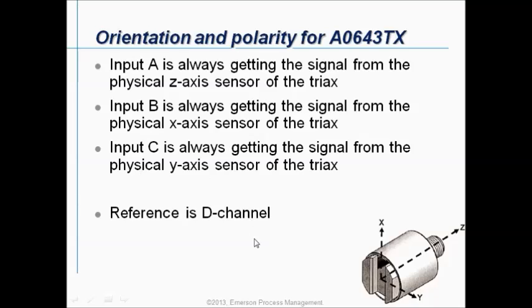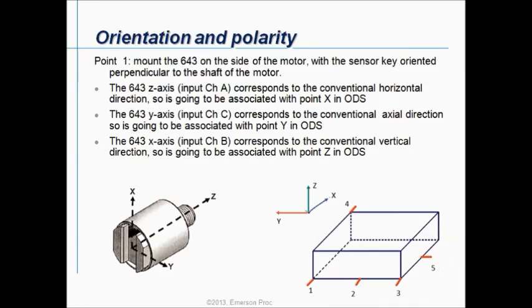Input C always gets the signal from the physical Y axis sensor of the triax, so this will be your C. The reference sensor for your ODS or modal job will always be connected to the D channel. What is very important inside an ODS or modal job is the convention of the orientation and the polarity of your axis. You have a lot of flexibility and freedom to customize and configure it how you prefer, but during this tutorial we will only explain the basics of the convention and show you one example.